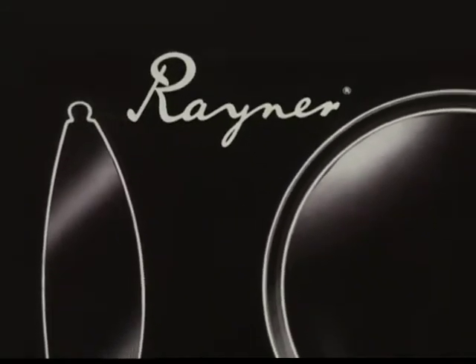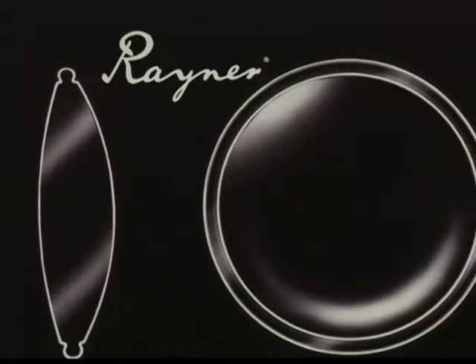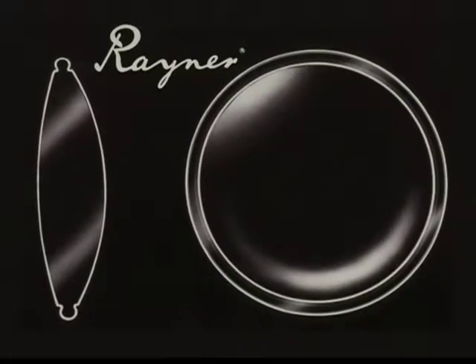But Pike and Ridley had copied too closely the radii of curvature of the human lens, and the lens power was too great, so the first two patients became highly myopic. Also, the lens was very heavy, weighing 112 milligrams in air, compared with approximately 5 milligrams for a modern implant.